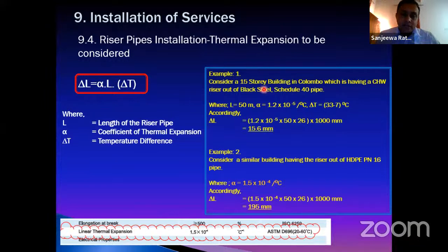For example, consider a 15-story building in the Colombo area, which has a chilled water riser of black steel pipes. We can consider the 15 stories as 50 meters of height. For steel, the coefficient of thermal expansion alpha is 1.2 times 10 to the power minus 5. And delta T, for a chilled water circuit, we can consider as 33 minus 7. Accordingly, we have to accommodate an expansion of 15.6 millimeters, so we have to keep provision for that.